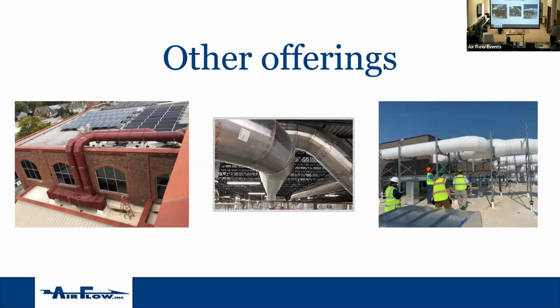When it's in round, it's leakage class 1. And it's also available in oval. So again, your tight spaces, contractors are going to want to put in their own stuff. I don't blame them. If I had a coil line, I'd want to keep my coil line running. If I had a spiral machine, I'd want to keep my spiral machine running. However, if you're in a tight space or you want a tighter spec, whatever the owner wants, this is available.